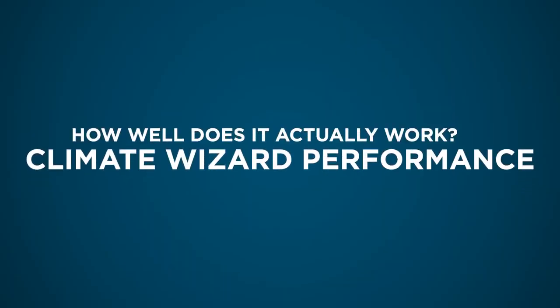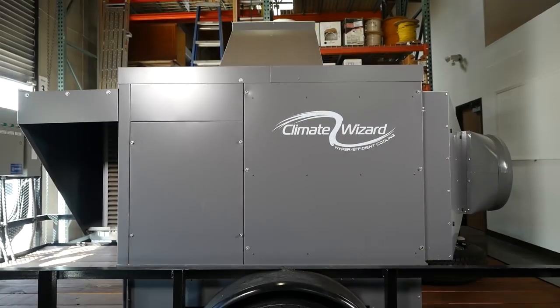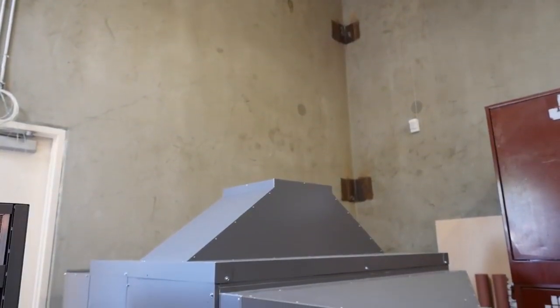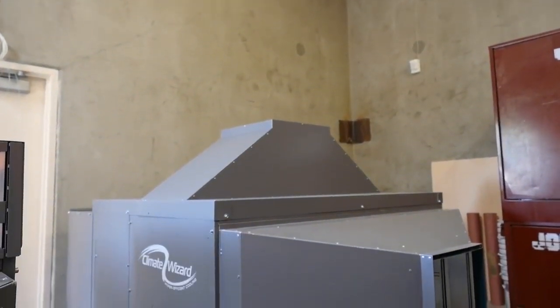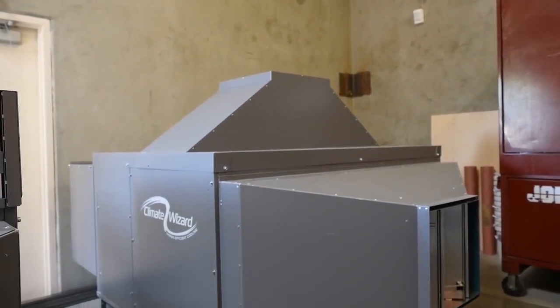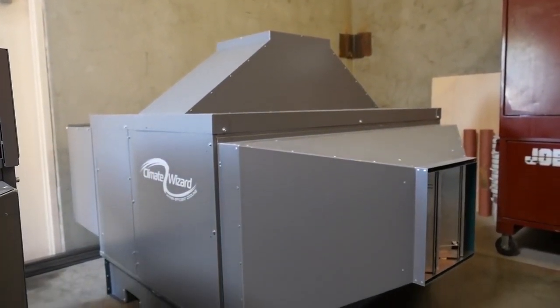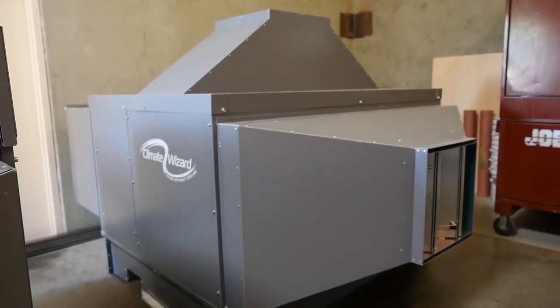Everybody has doubts first. What we had to do is monitor it, put the control system in so they could see instantly on their computers what the outside ambient is and what the supply temperature was. Seeing is believing. We actually brought the units into our office and did extensive testing on them. And so we saw what it could do with ambience in the range of 115 degrees. We built our own model, got the ambient up to 130 degrees. We're still supplying supply temperature in the range of 55 degrees.